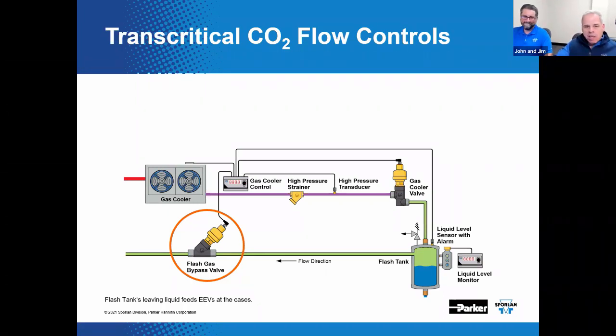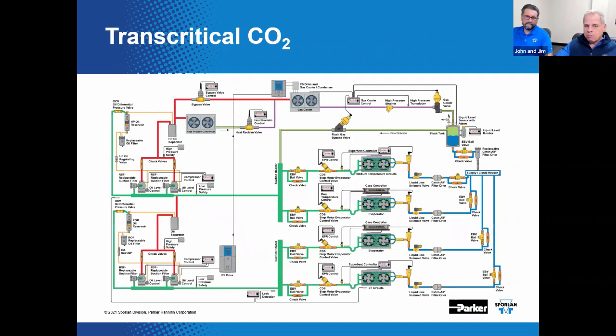I'll tell you. Located on the vapor line leaving the flash tank receiver, it regulates the pressure on the low side, with the flow of saturated CO2 vapor taking place. The valve outlet is connected to the compressor suction line. So, CO2, there you have an abbreviated discussion on the application of transcritical CO2.